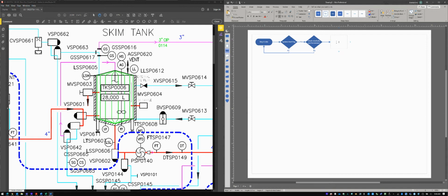Anytime we need our system to have different outputs, that means we need a different step. Our idle is going to be basically everything off. All the valves are shut, the pumps are off, the glycol's off, all that other stuff. And then when we see it start up, we're going to change our outputs so that we are doing something specific.